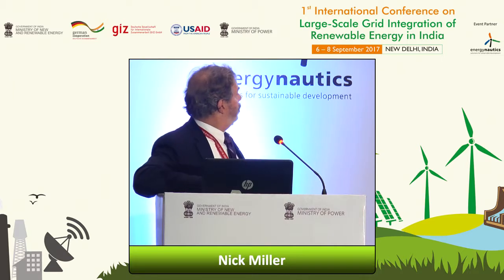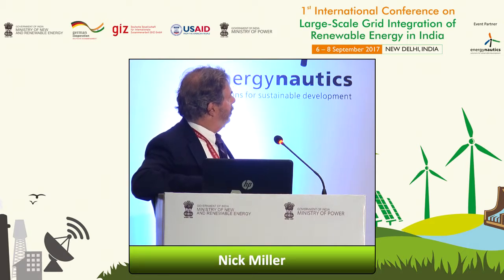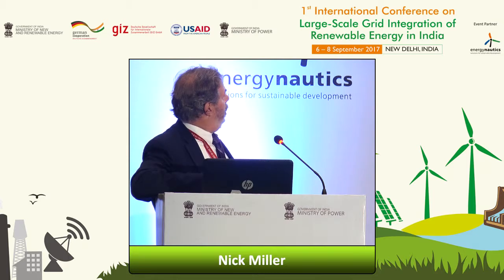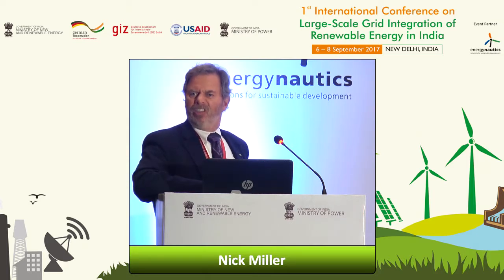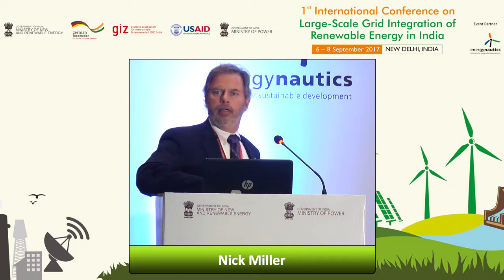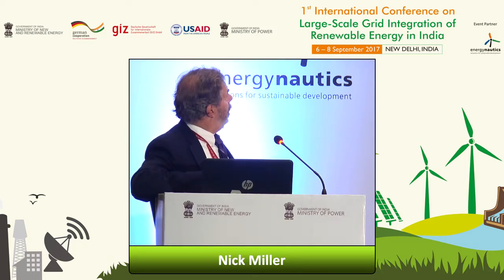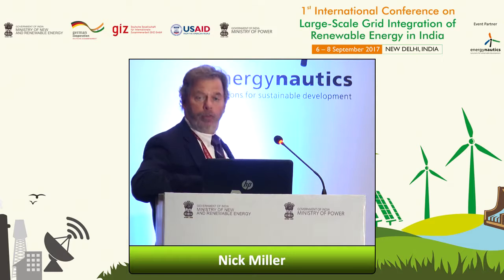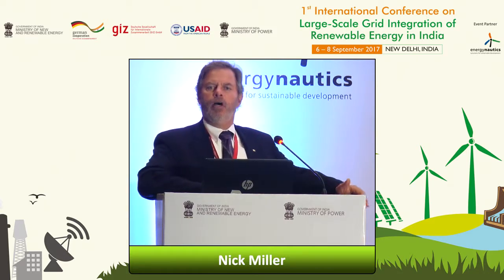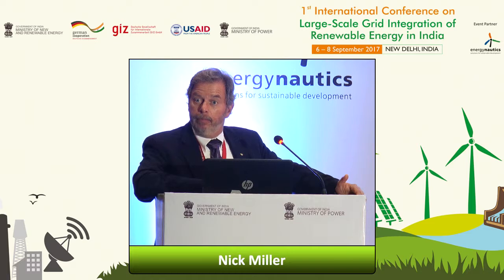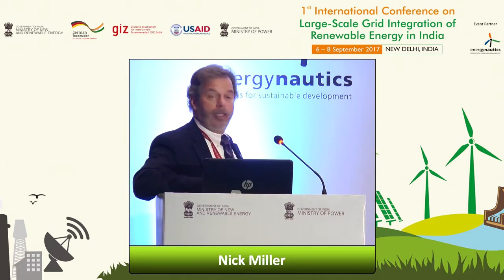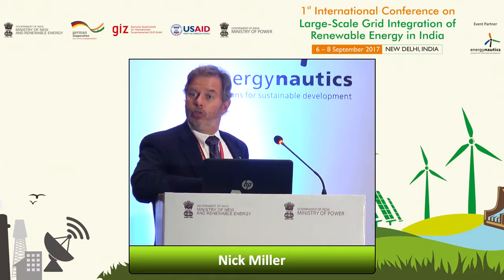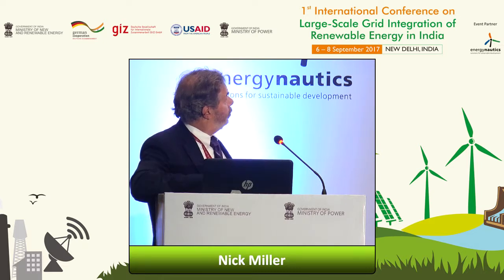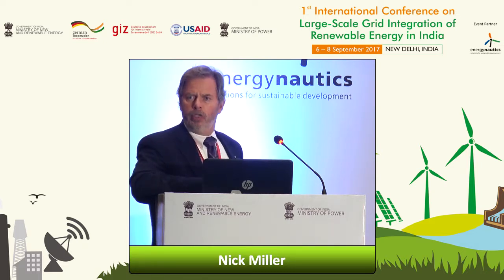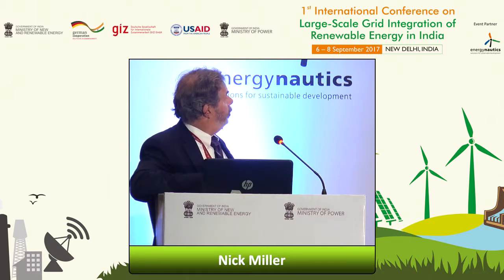This is an hour measurement. I know you can't read the axes, but this is an hour - a swing of about 30 megawatts, so it's a fairly ugly hour. The blue line is the voltage at the point of interconnection, 75 kilometers from the wind plant. This is a US 60 hertz system at 230 kV, so one division, which I hope you can see, is 1 kV.